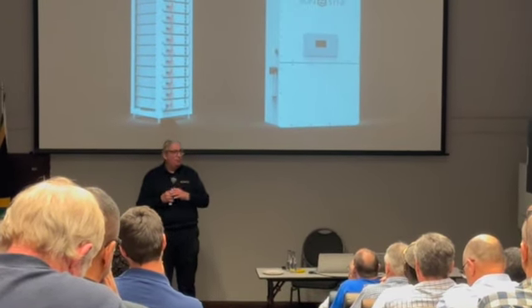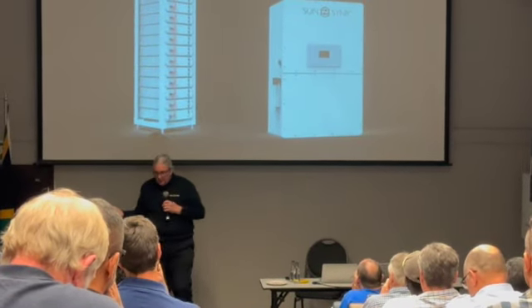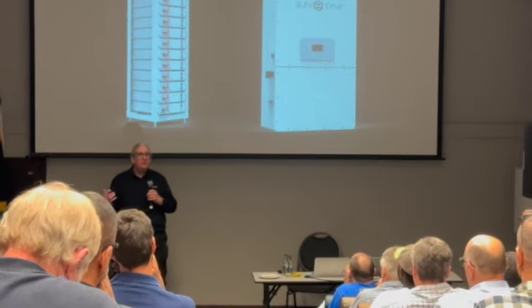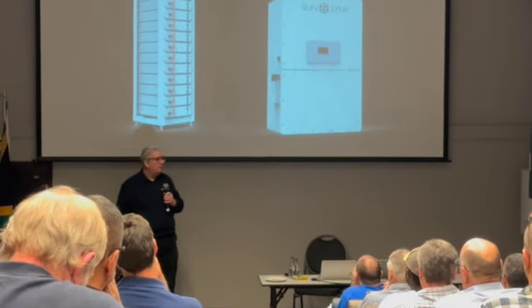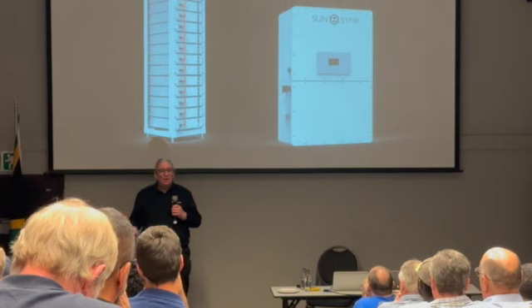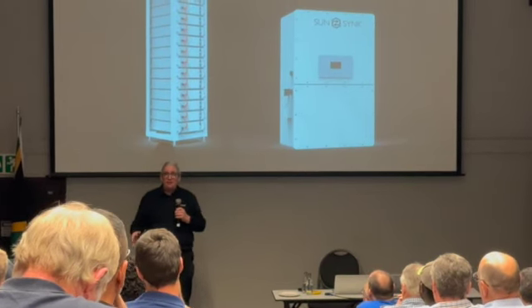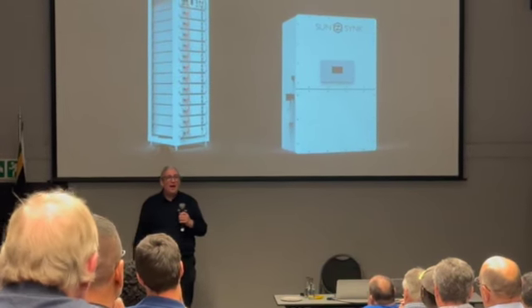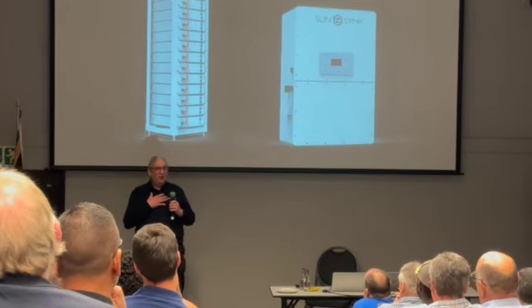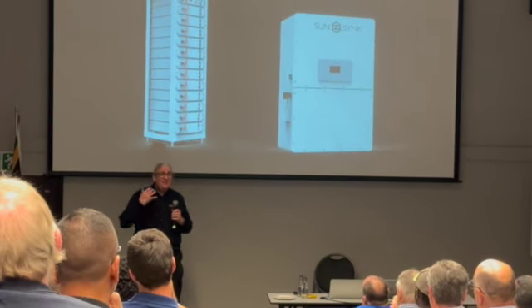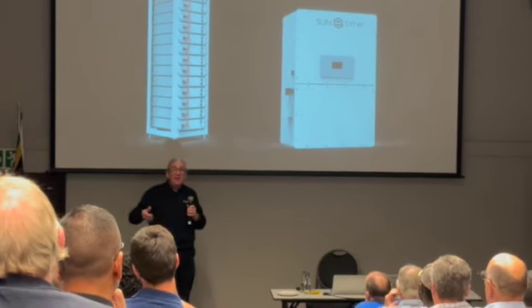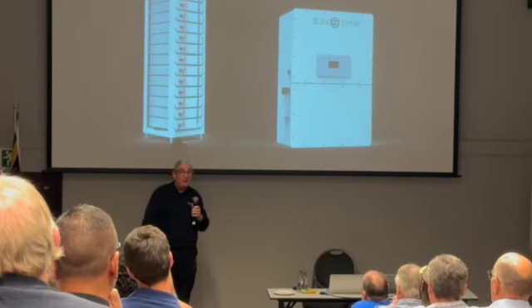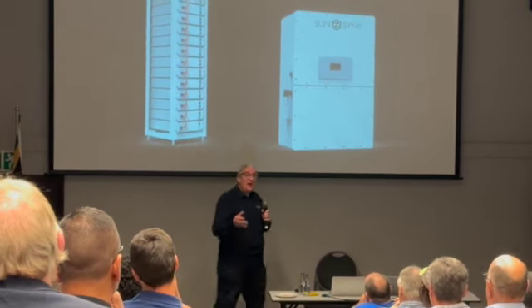A good example: we were in Hong Kong, there's a company doing container batteries and they're using a low frequency inverter, about 500 kilowatt. It was burning 7,000 watts and they called it idling - I call it quiescent power. It was burning 7,000 watts and doing nothing. They had to run a generator to keep the inverter working. It's ridiculous, and that's the problem.